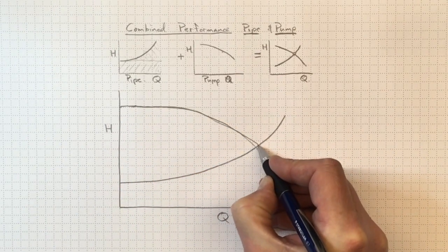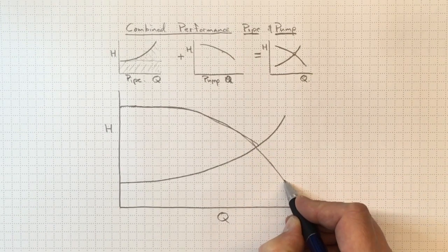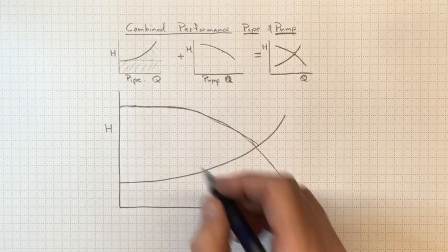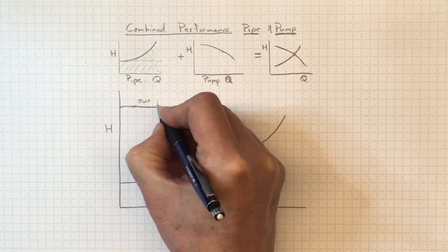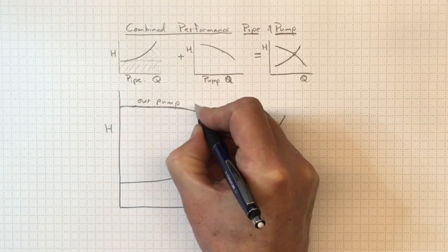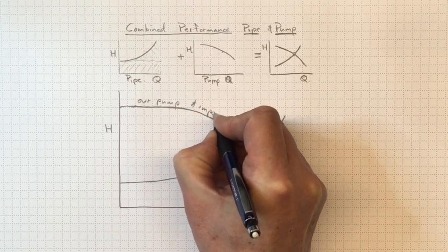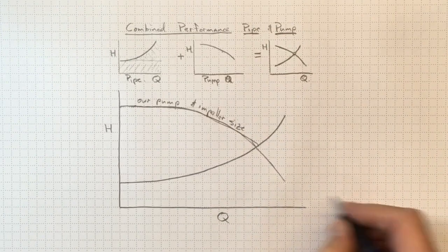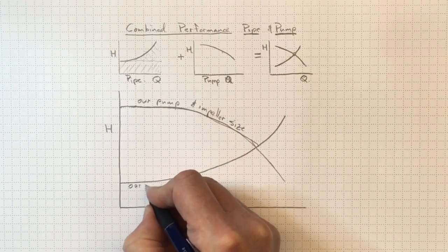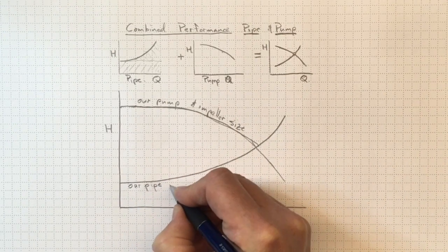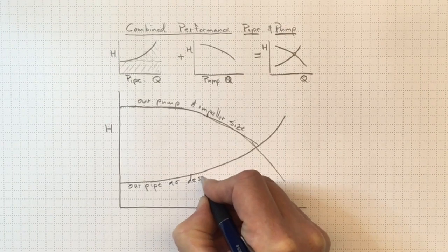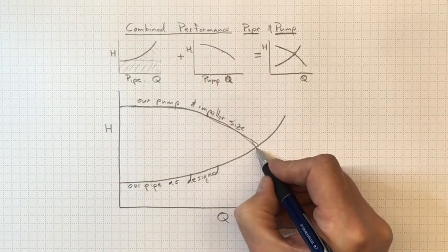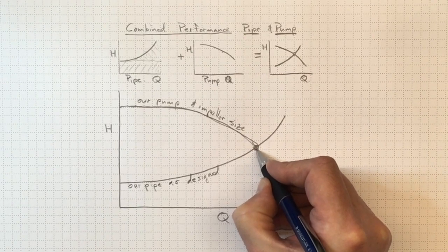We've taken this off the manufacturer's curve. We've ignored the other impeller sizes. We've only got the impeller size that we're going to use. So this is our pump that we've picked with the impeller size that we've picked, and this is our pipe with all of its fittings and everything as we've designed it. And when we put them together, this is where we expect our operating point to be.